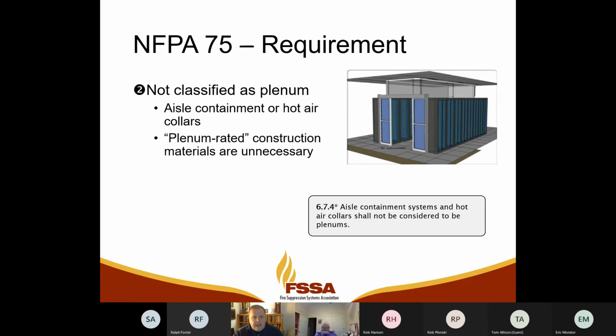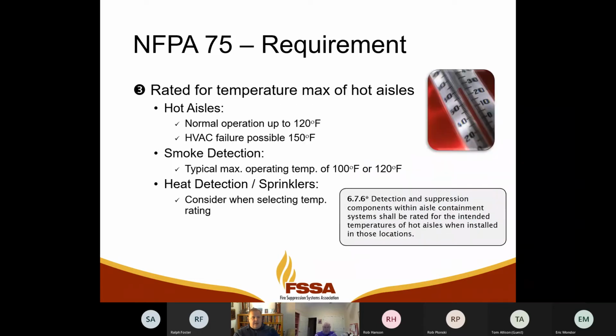It's very clear in the new requirements that these areas are not classified as plenums, so you don't have to have plenum rated cable, and that's a big deal in data centers because of all of the low voltage cables, whether it's network cable, fiber optic cable, or power cables to the individual pieces of IT equipment. A lot of those manufacturers don't make plenum rated cables, and if you did have to purchase plenum rated cables, it would significantly increase the cost of data centers just because of the amount of wires. So NFPA 75 is clear that plenum rated construction materials are unnecessary inside of areas of aisle containment.